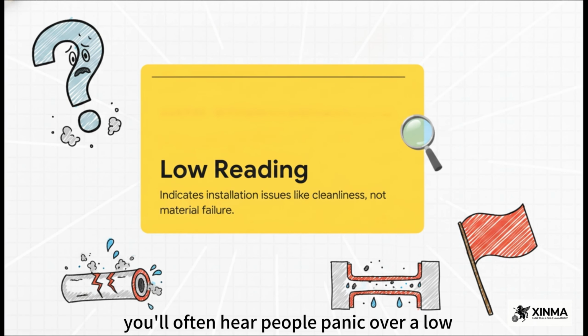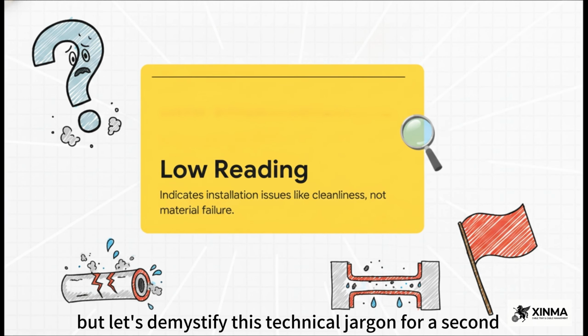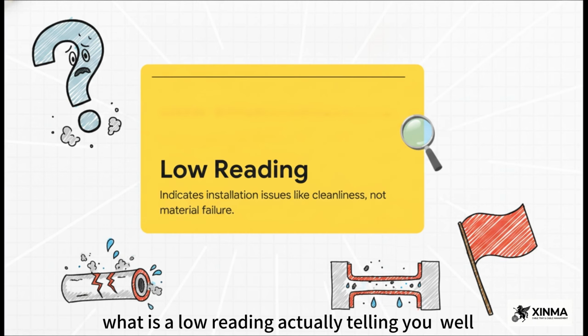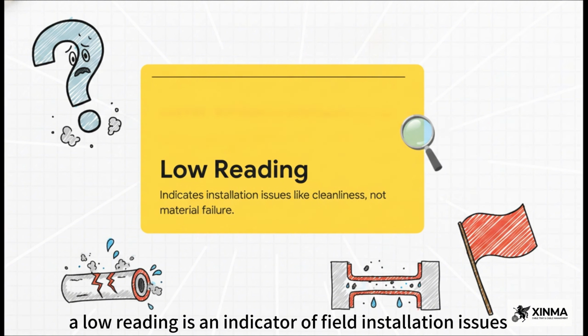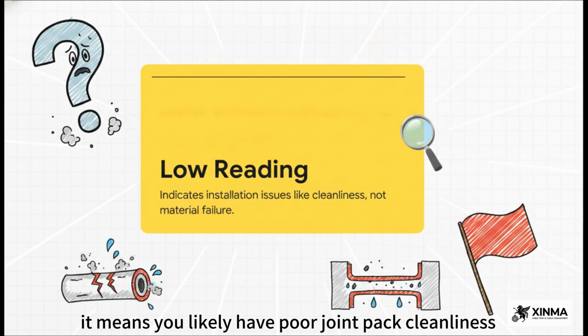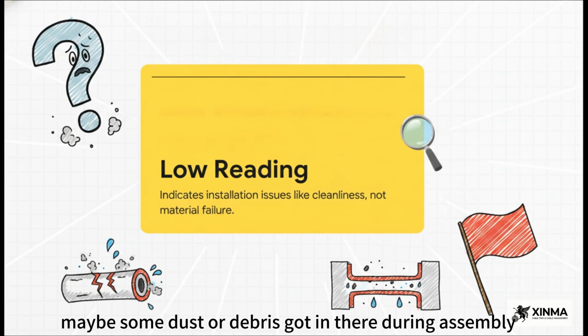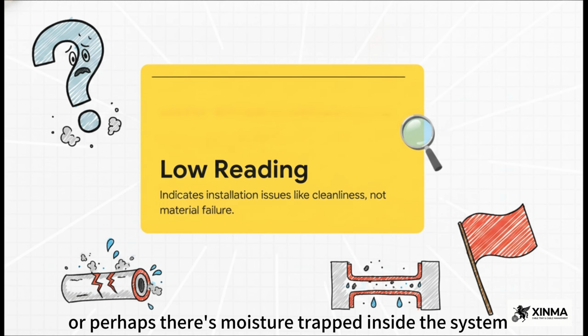You'll often hear people panic over a low reading during an insulation resistance test, but let's demystify this technical jargon for a second. What is a low reading actually telling you? Well, a low reading is an indicator of field installation issues. It means you likely have poor joint pack cleanliness, maybe some dust or debris got in there during assembly, or perhaps there's moisture trapped inside the system.